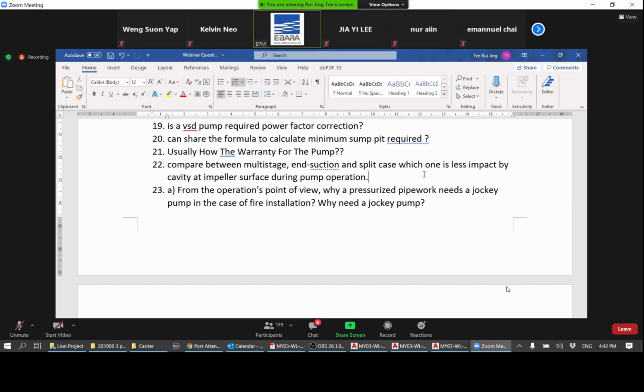I would say that a split case has probably the best NPSH value and also the best suction capability. As I mentioned earlier, a split case has a double suction, which means that it is able to take suction from both sides of the impeller, and that will result in a much better suction compared to a multi-stage or end suction pump. If you just compare the pump curves, the NPSH value, you will see that normally a split case pump has a much lower NPSH required than other pumps.